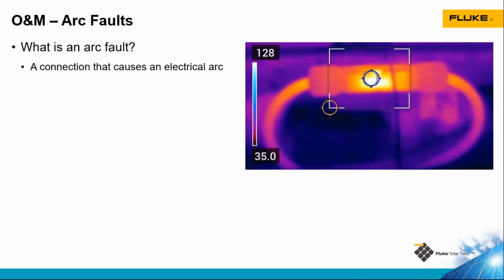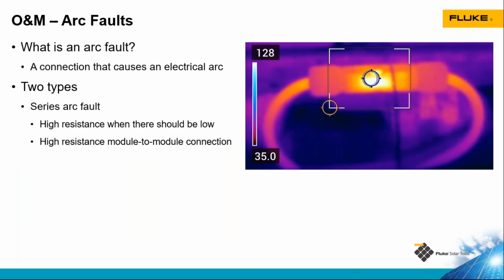Now, another problem we have in solar arrays are arc faults. Arc faults are an electrical connection that is arcing. There's two types of arc faults. A series arc fault is a situation where I have a high resistance connection when I want a low resistance connection. And that could be a circuit with two connectors in it, like a module interconnection, where there's a high resistance between those two connectors where I want an easy path for the current to flow. This thermal image here is an example of a connector that was at a higher temperature than other connectors in the system under the same environmental conditions, indicating that there's arcing in there, which is giving off heat.